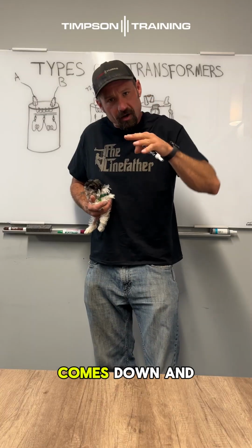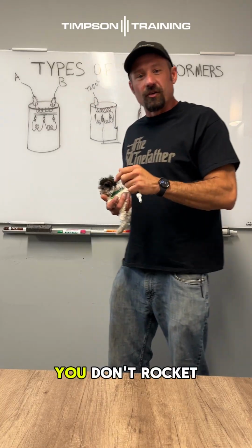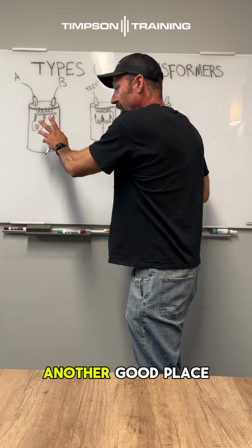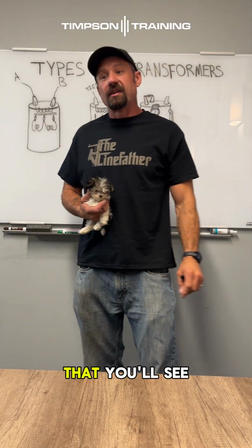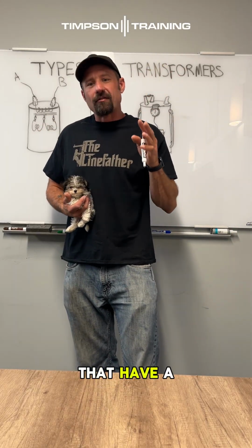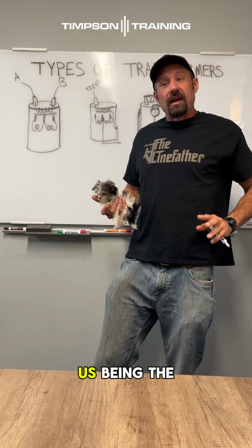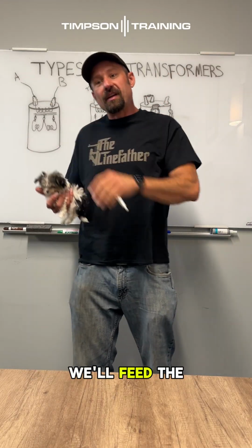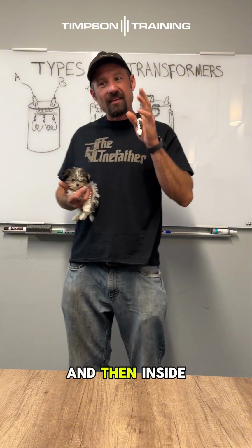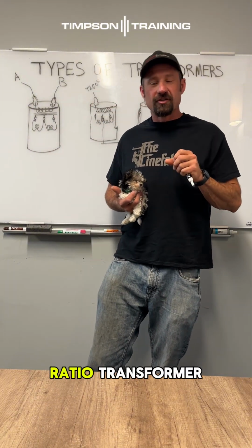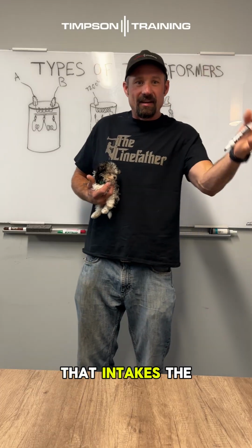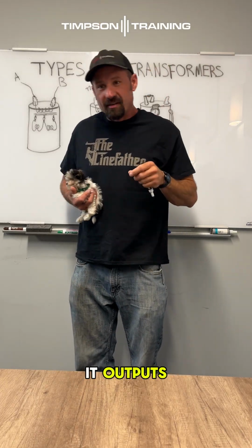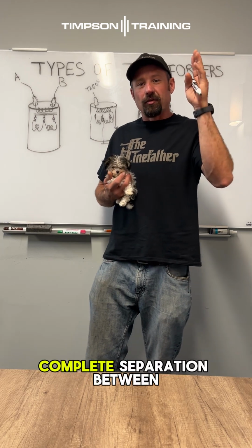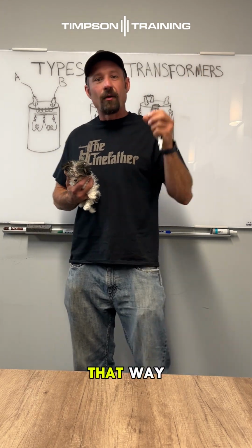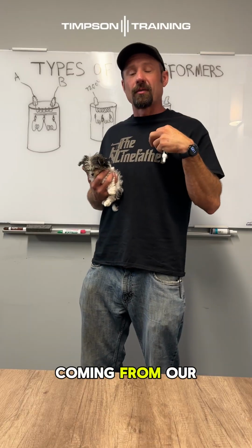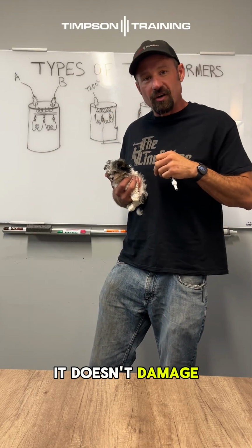That way if the 34 comes down and touches the 12, you don't rocket meters off the side of houses. Another good place for isolation transformers that you'll see is in facilities that have a lot of really sensitive equipment. Us being the power company or the contractor, we'll feed the power into the building, and then inside the building, they'll have a 1-to-1 ratio transformer that intakes the same voltage as it outputs, but it's isolation. So there's a complete separation between coils. That way, if there's a power surge coming from our side, it doesn't damage their equipment.